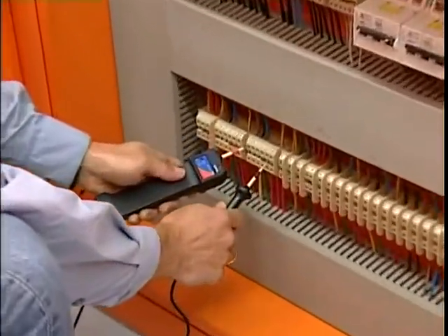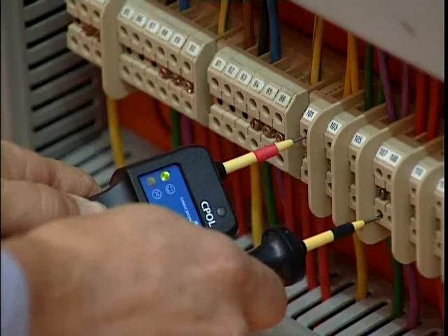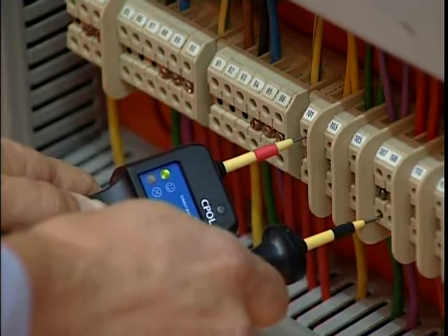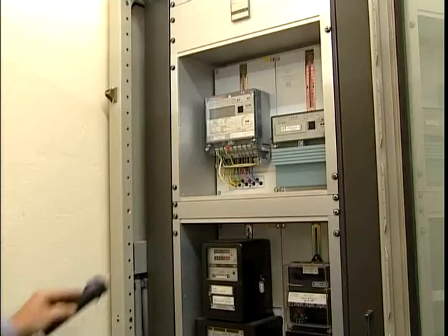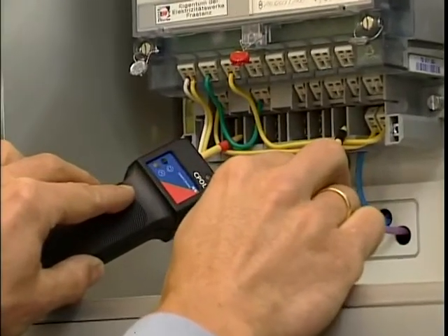The CPC allows for a completely new way of testing due to state-of-the-art amplifier technology. Instead of using a sinusoidal output signal, sawtooth waveforms are generated. The rising and the falling edge have a different slope.